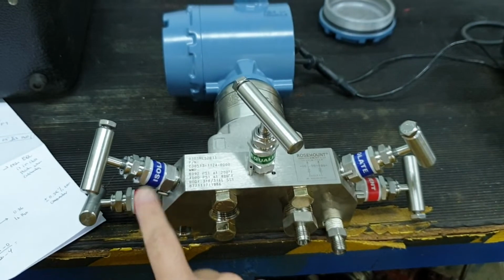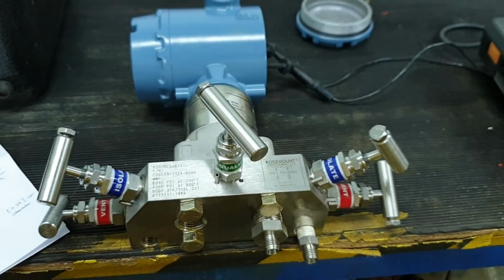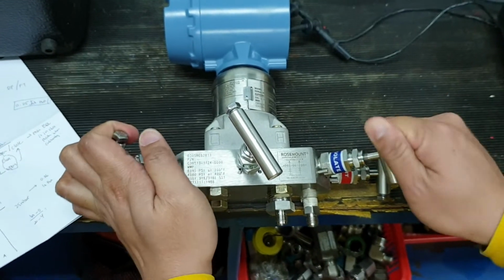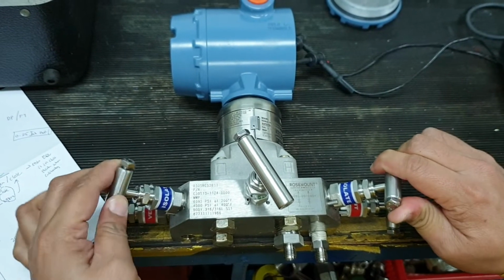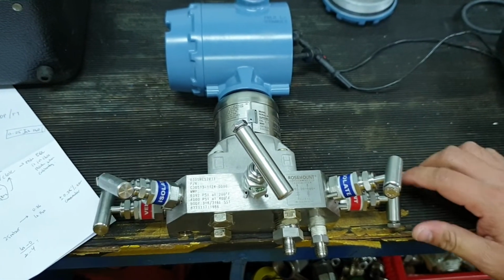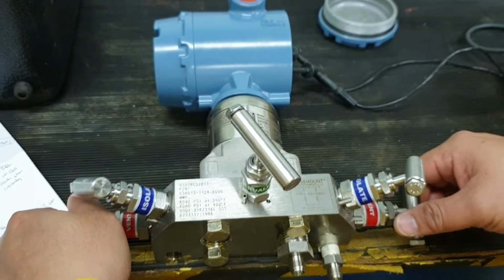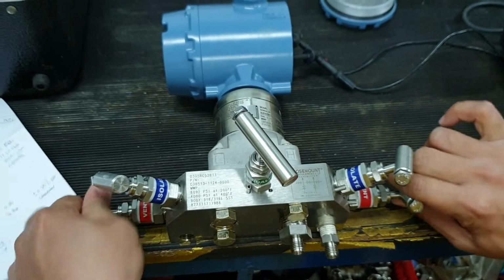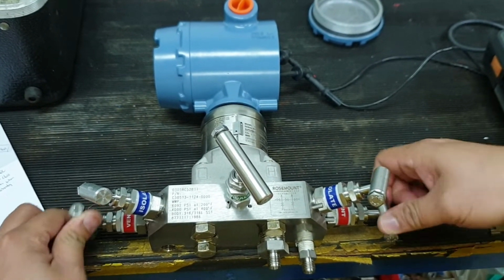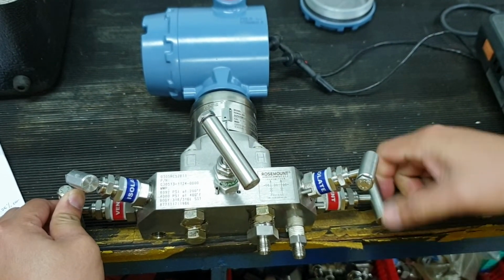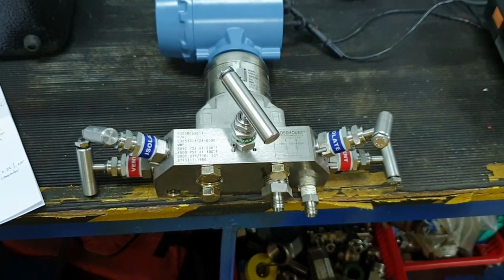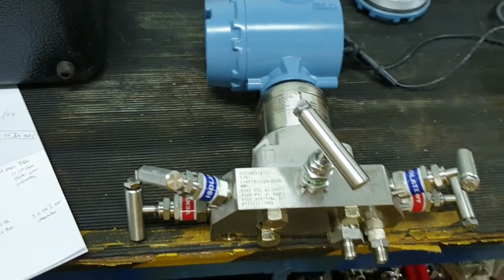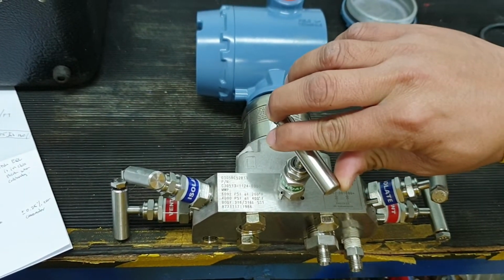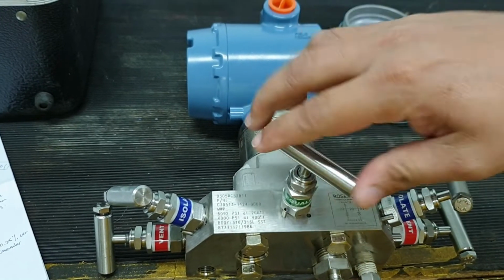After that, we're going to close this isolate valve. Once the isolate valve is fully closed, we proceed to open the vent valve, fully open the vent valve. Once done, we will close the equalize valve, fully close the equalize valve. The reason why we opened it in the first place is to ensure that there is no damage to the internal diaphragm of the transmitter.